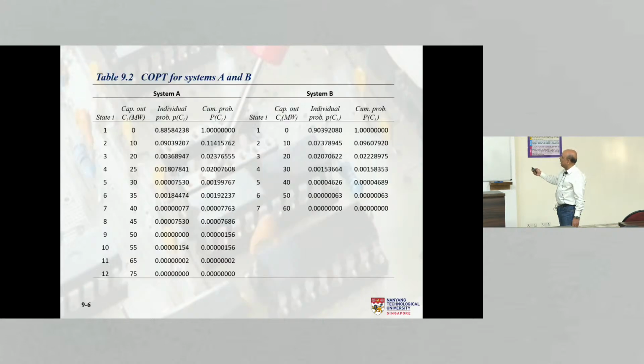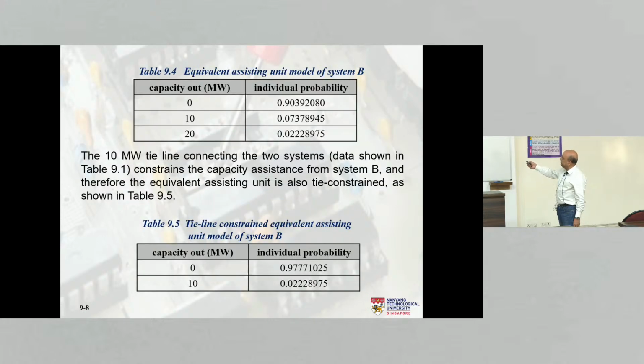So even though I have a support of up to 20 megawatt, capacity out 0 means I have 20 available, right? But I cannot get 20 because the tie line is constrained to 10. So when it is in this state, I'm getting only 10. When it is in this state, I'm getting only 10. When it is in this state, I'm not getting anything. Correct? So for these 2 states, I'm getting 10 megawatt. Therefore, the probability is this plus this. That means 0.97. And for the last state, the probability is this. So this is like a 2-state equivalent assisting unit after having passed through the tie line.